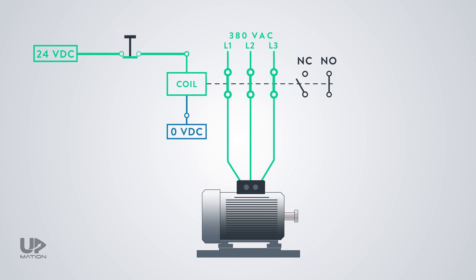As these types of actuators are mostly used in case of emergency and safety, then we should always be confident about their circuit functionality. To do so, we use normally closed contacts and therefore, the same as the previous example, when any cable damage happens, the circuit will be opened and the process will be stopped.